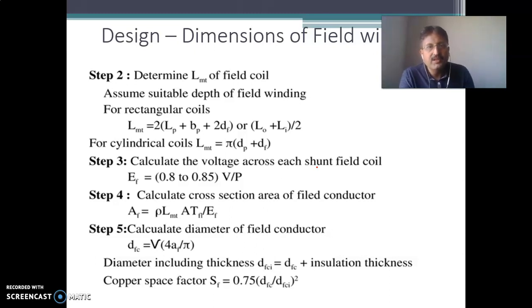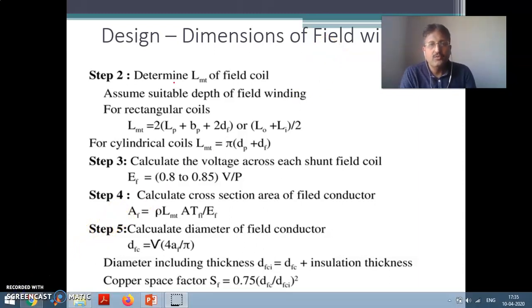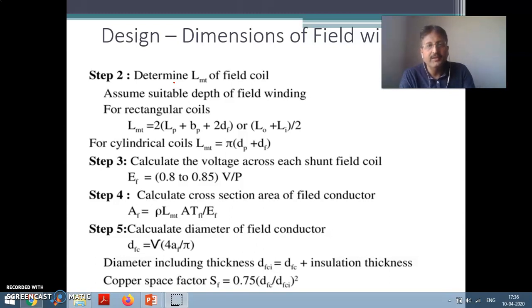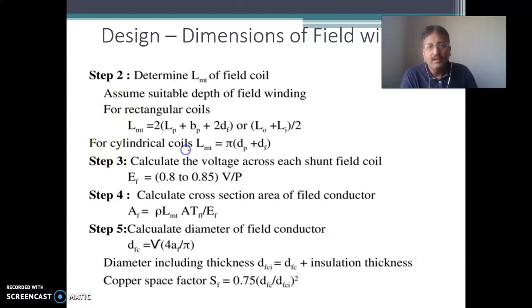The second important part is the design and dimension of the field winding. The task is to find out the length of mean turn (LMT) for the shunt field coil. When you wind the first turn around the pole it has the minimum length, and the outermost has the maximum length. For a cylindrical or circular coil, LMT = π × d. For a rectangular coil, it is LMT = (L_O + L_I) / 2.